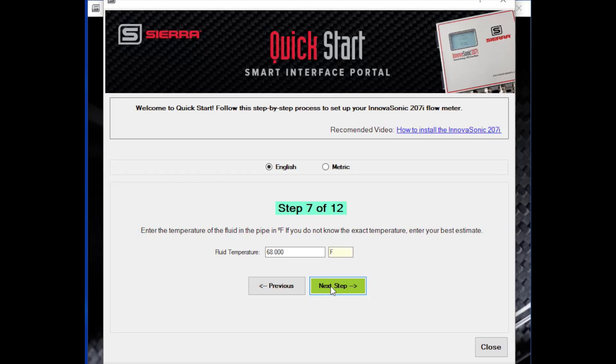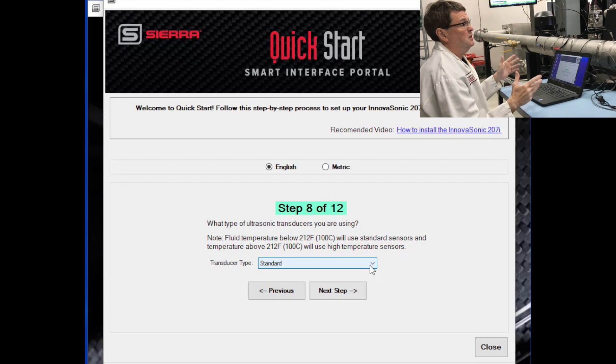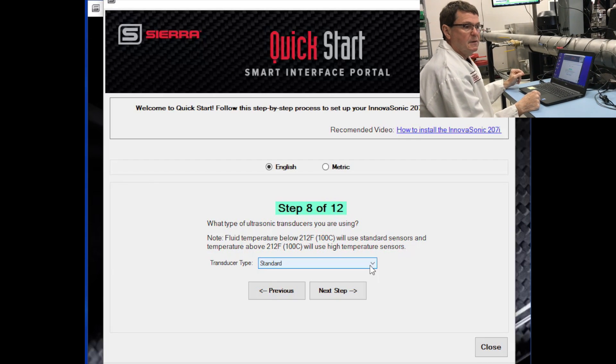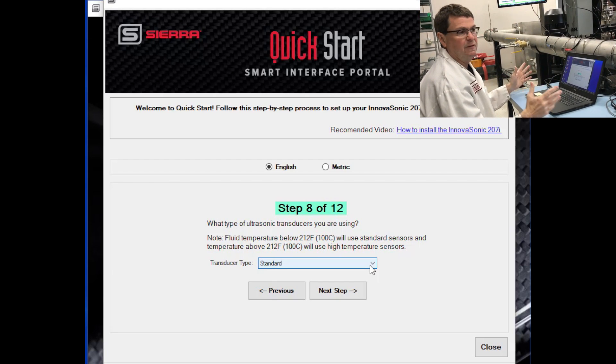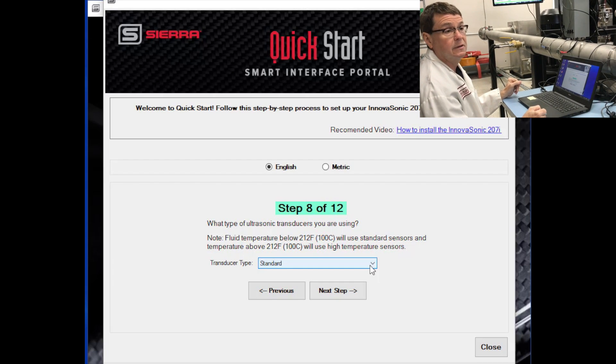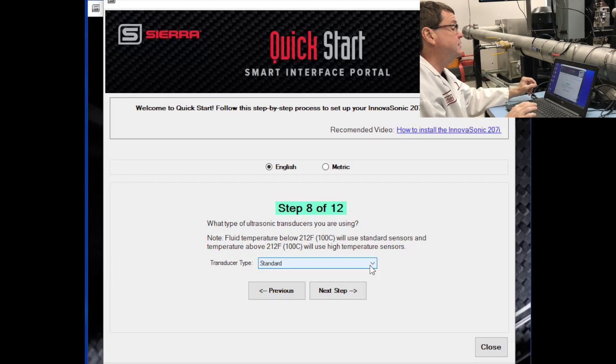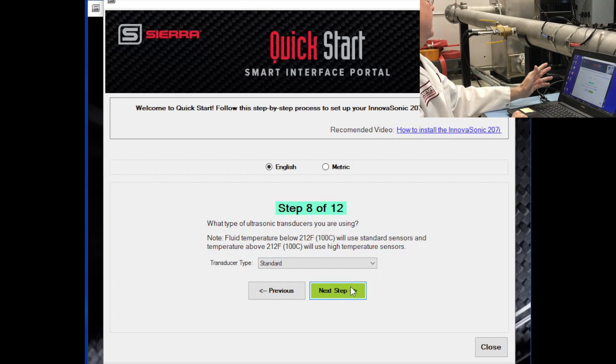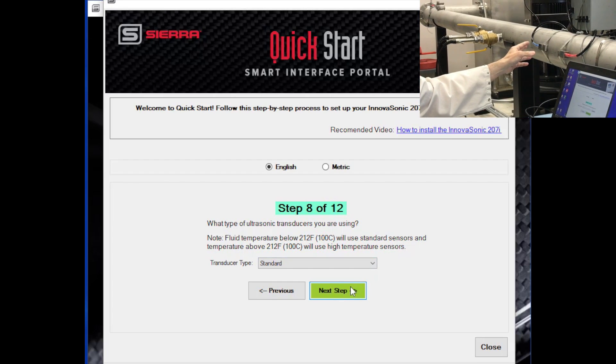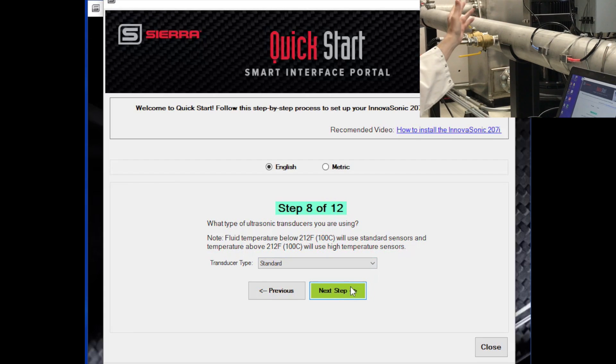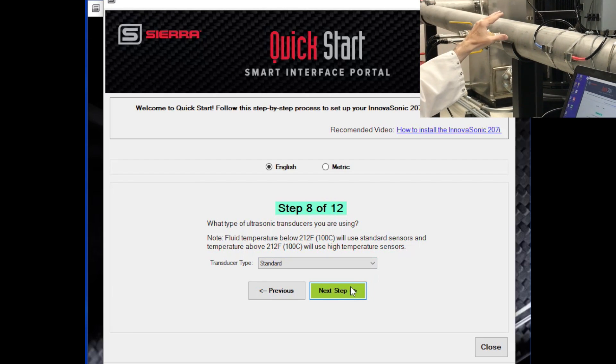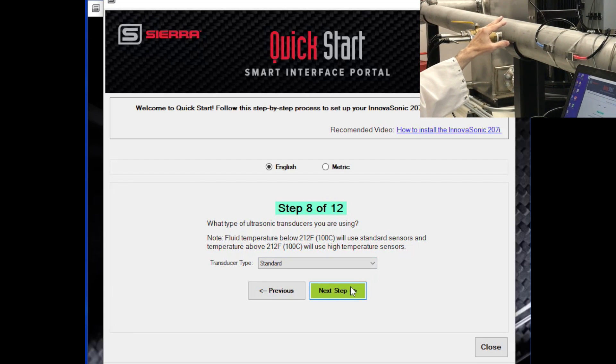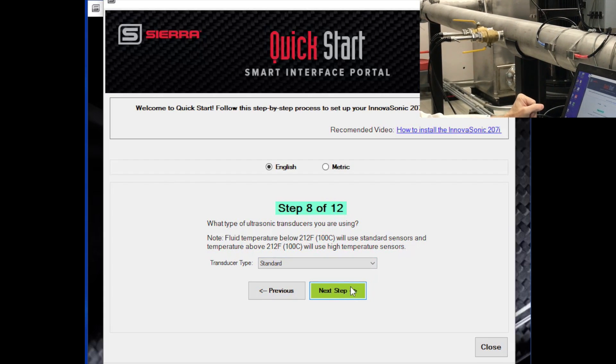The next step is what is the temperature of the fluid inside the pipe. Now the meter can actually measure that if you have the optional temperature inputs, or you can tell the meter what the temperature is at this point. So enter that. Step eight, you need to identify whether you're using a standard temperature version or a high temperature version. The standard versions are available in clamp-on and insertion. The high temperature version, we have clamp-on versions of that. For example, I have the clamp-on transducers here clamped onto the pipe. I have a set of insertion transducers as well that insert through the pipe wall into the fluid itself.